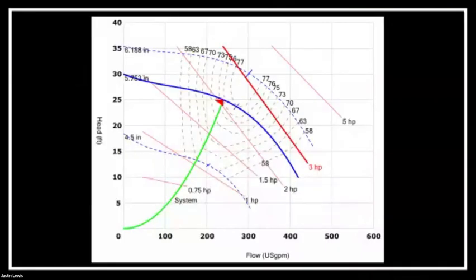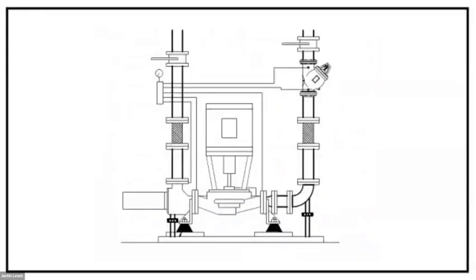So we'll start with pumps. This is a common pump curve, and pump curves are commonly used to verify pump performance. The chart references a pressure drop across the pump at a specific operating condition. Now, when we talk about pressure drop across the pump, we are specifically talking about pressure drop across the pump. We're not talking about a pressure drop prior to the strainer and at the check valve or triple duty valve. We're talking about directly in and out of the pump. We need to make sure that we have these test ports or this gauge assembly installed in the right location, or our readings are not going to be reflective of the provided pump curve.